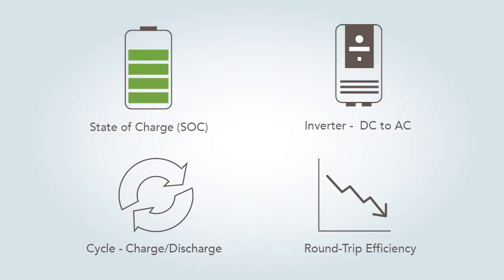A cycle just means when you do a full discharge and a full charge. So if you look at a spec sheet and it says about 3,000 cycles or 5,000 cycles, you can get an idea of how long the battery will last. If you cycle it every day, 365 days a year, and you have 3,000 cycles, you'll probably only get 7 or 8 years out of that battery. Some are about 5,000 cycles, so you'll probably get a bit longer than that.